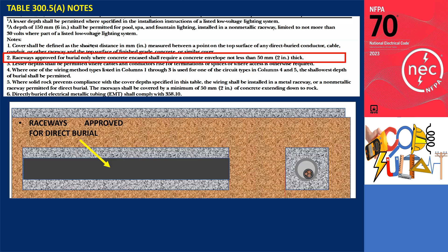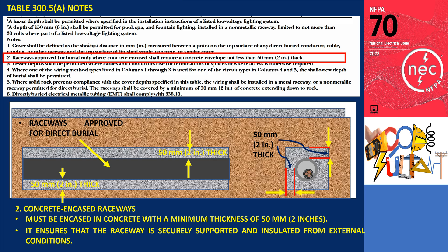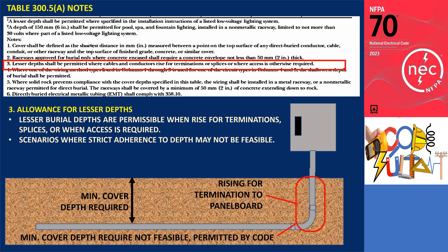Note 2: Raceways approved for burial only where concrete-encased shall require a concrete envelope not less than 50 millimeters (2 inches) thick. This concrete envelope provides additional protection against physical damage, environmental factors, and ground movement, ensuring the raceway is securely supported and insulated from external conditions — particularly important in areas subject to heavy loads or disturbances. Note 3: A lesser depth shall be permitted where cables and conductors rise for terminations or splices or where access is otherwise required. If conductors in direct burial cable or raceway come up to terminations or splices in boxes or equipment, the required depth cannot always be maintained. This flexibility acknowledges practical installation scenarios where strict adherence to depth may not be feasible.